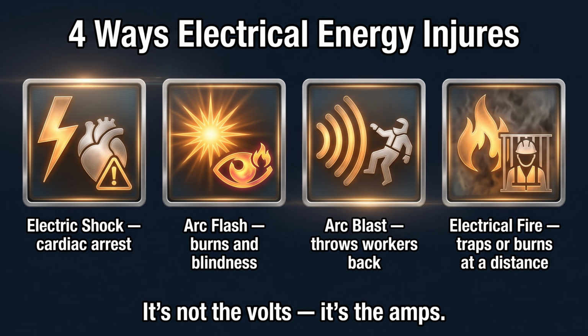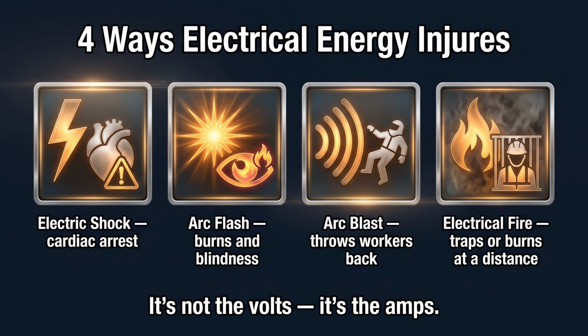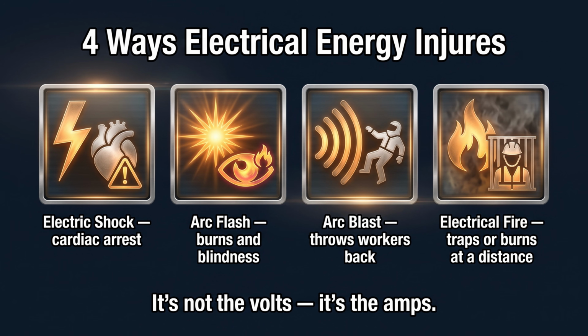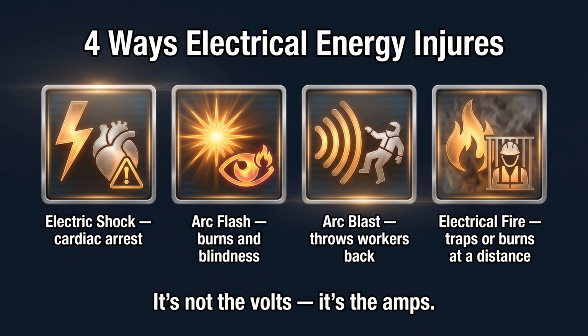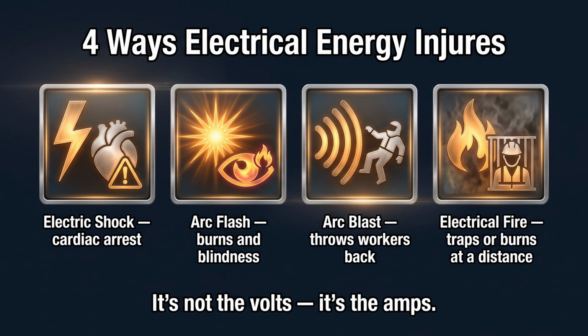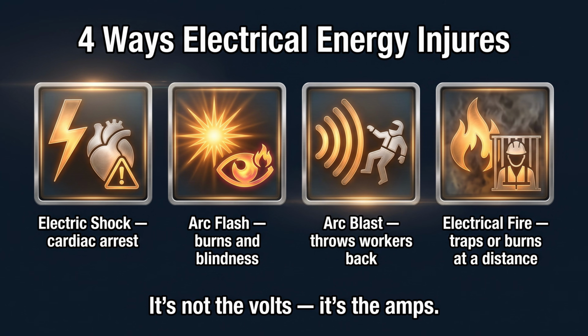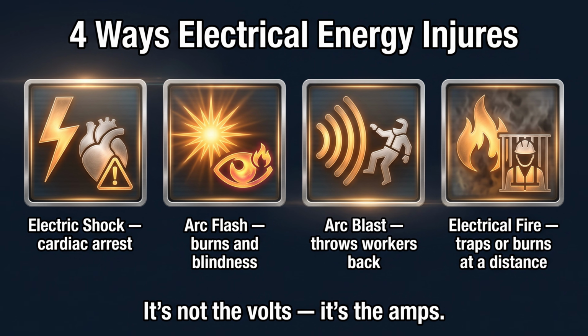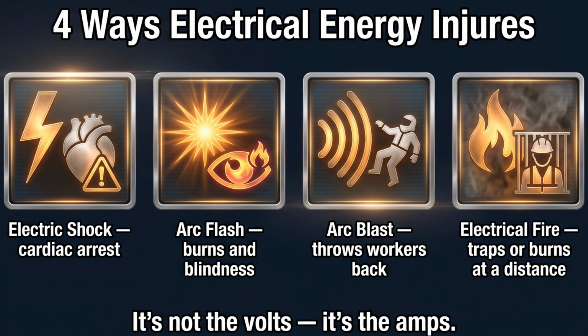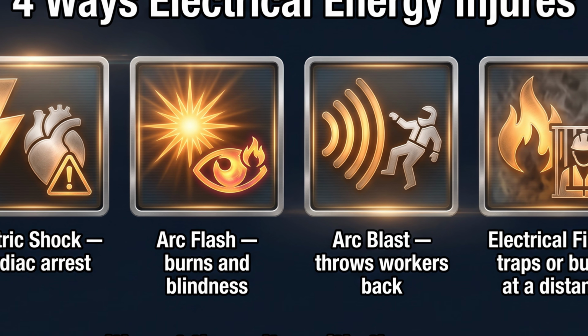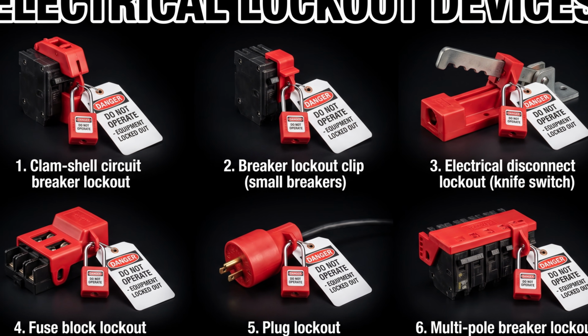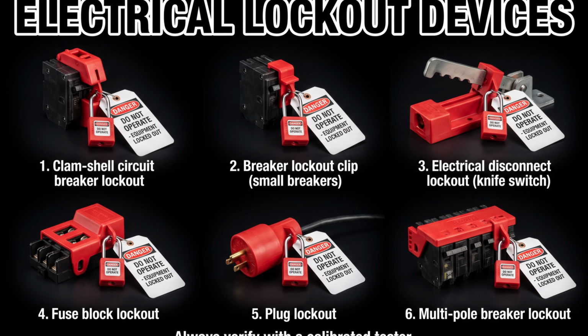Electric shock. Current passing through the body can cause cardiac arrest, respiratory failure, nerve damage, and severe burns even at relatively low voltages. Arc flash causes third-degree burns and blindness. Arc blast. The pressure wave from an arc flash event can throw workers across a room. And electrical fires can trap or burn workers at a distance. Remember, it's not the volts that kill, it's the amps. Controlling electrical energy requires isolating it at the source and verifying zero state.